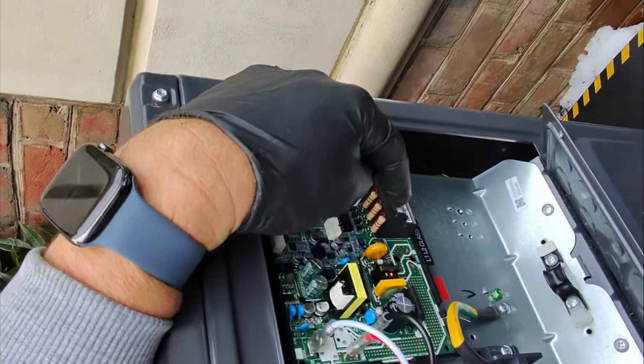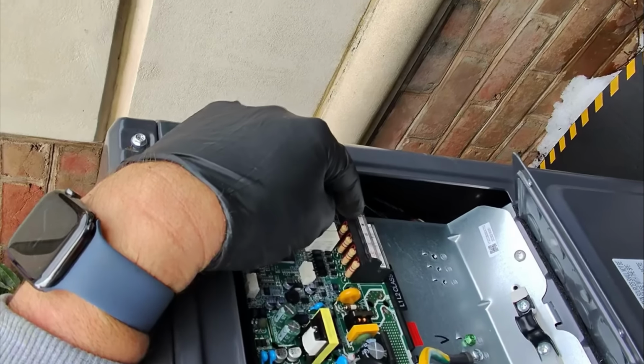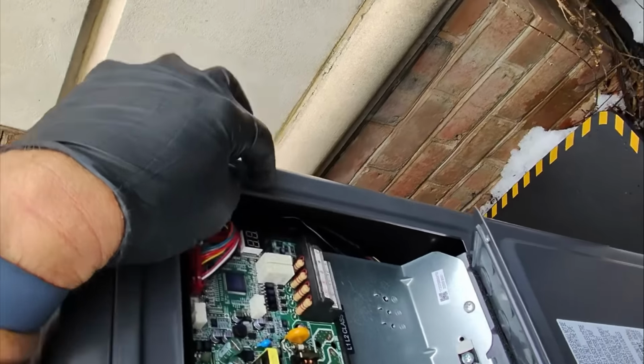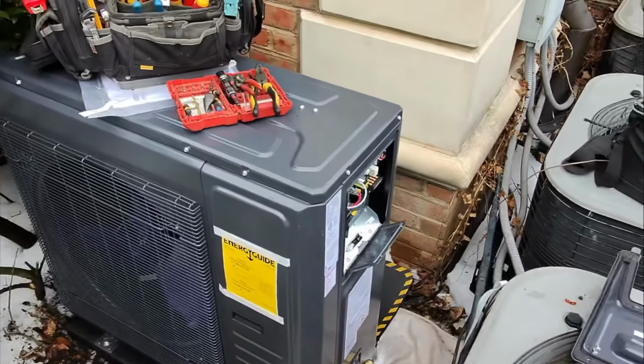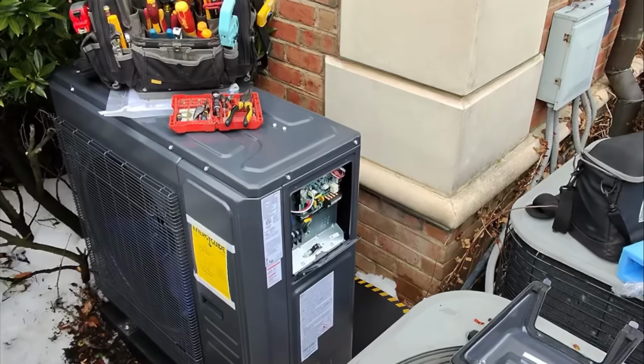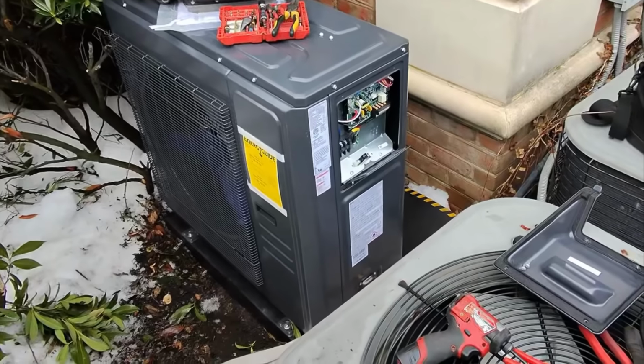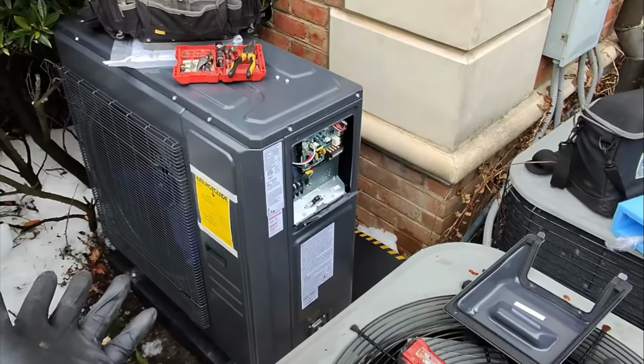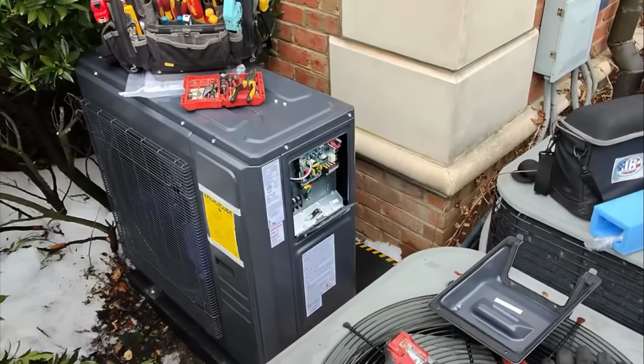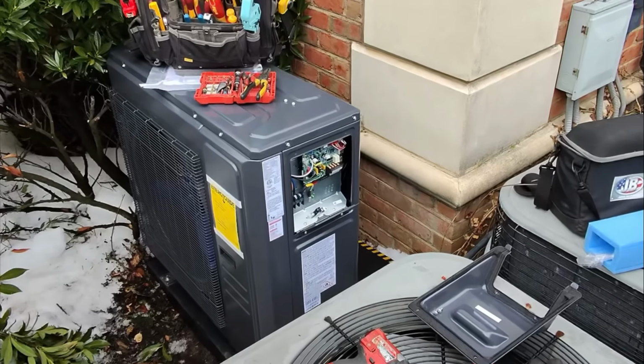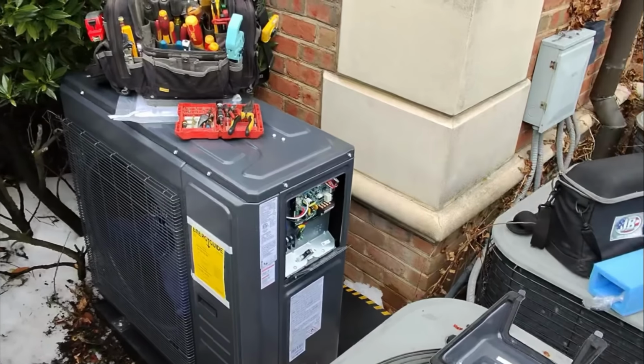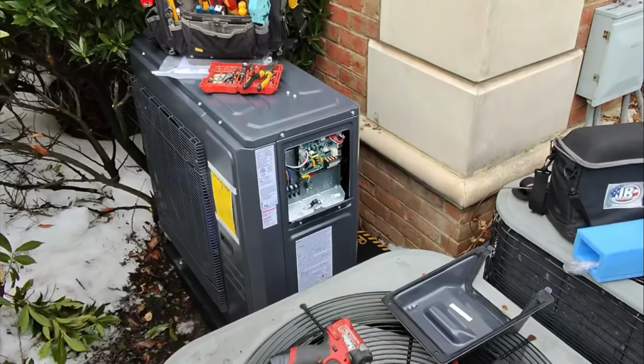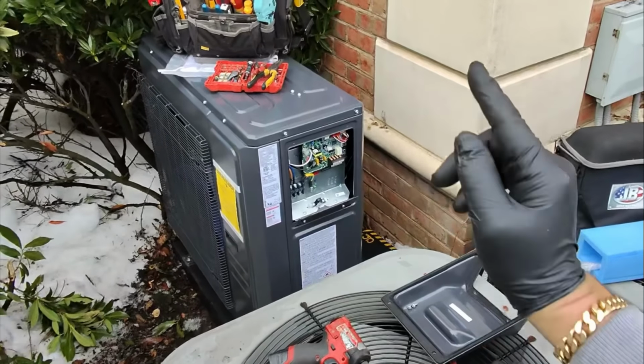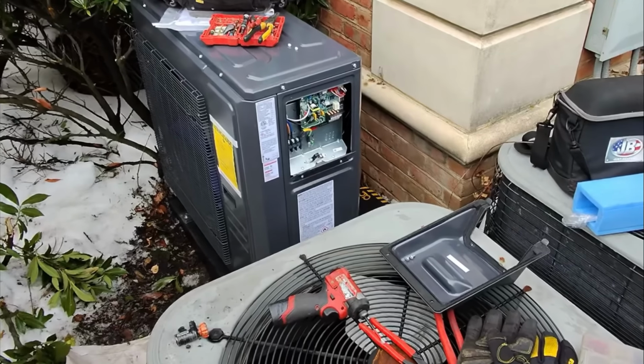We can do our traditional R, C, Y1 or Y2, B, or we can do communicating with S1, S2 right there. This is a perfect system to install if you're unable to replace the control wire from the indoor air handler to the outdoor unit, because if you're doing a straight cool to a heat pump, you need that extra wire for O/B. Here, if you're doing a communicating mode from the air handler to the outdoor unit, even if you use a 24 volt traditional thermostat, you're not going to have any problems, because all you need is S1, S2 on the outdoor unit, which connects to the indoor unit, and voila, you're done.